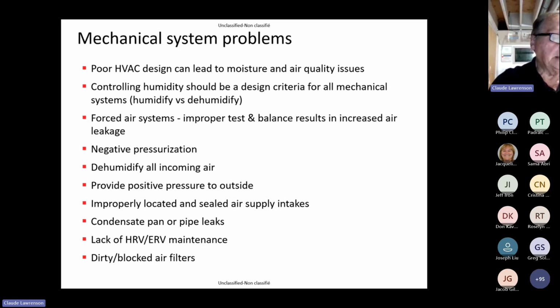By the way, unlike energy recovery ventilators, heat recovery ventilators do not reduce humidity in the home, but they can reduce the moisture by exhausting moist air out of the home. So again, poor HVAC design can lead to moisture and air quality issues. Controlling humidity should be a design criterion for all mechanical systems. With forced air systems, improper test and balance can result in increased air leakage. So again, if I drill down, a lack of HRV and ERV maintenance is also a big concern.